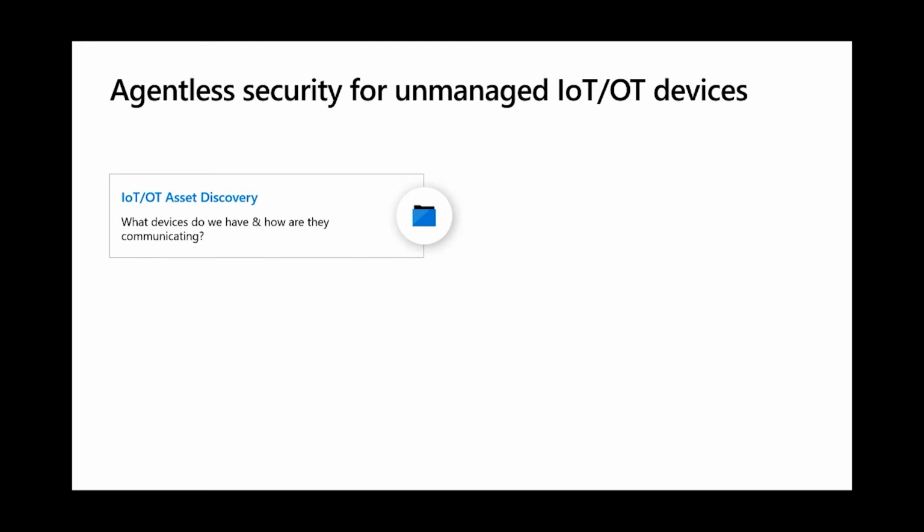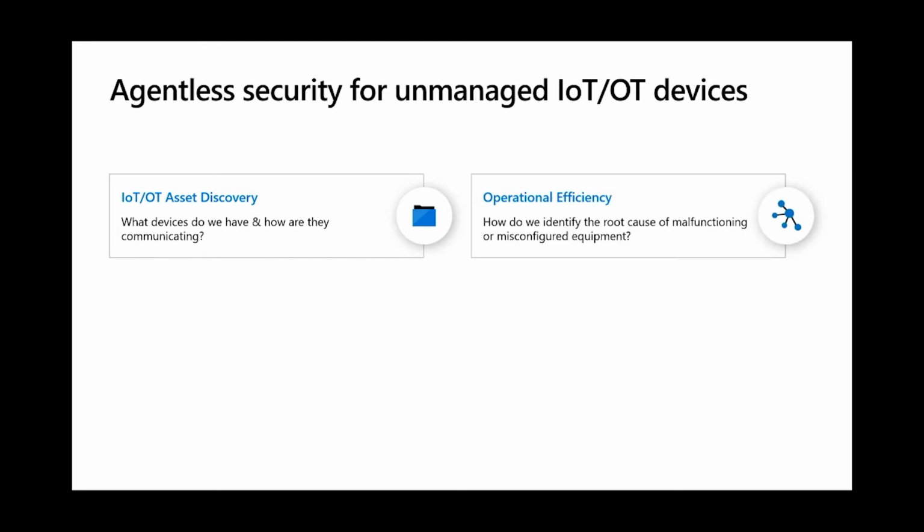The next step is to look at that map and understand that sometimes these devices only have one pathway. Now, they're generally designed with 2 pathways for everything, so you have the fault tolerance that if a network switch or a cable or something went down, a signal could still be received from a different path. You may find that by doing this network discovery, you'd run this for maybe 2 or 3 days, capture a PCAP file, ingest it, and you'd see in 3 days, this one device only talks to one other device. It only has one pathway, and all my other devices have 2 pathways.